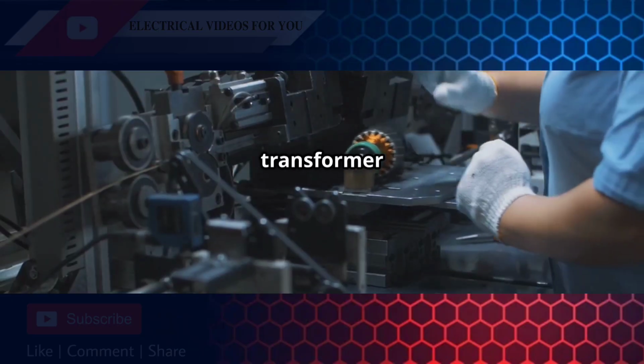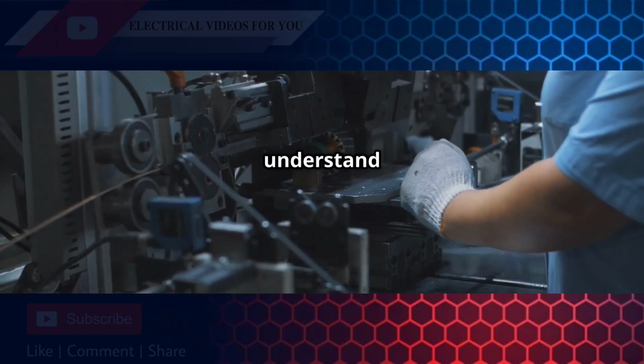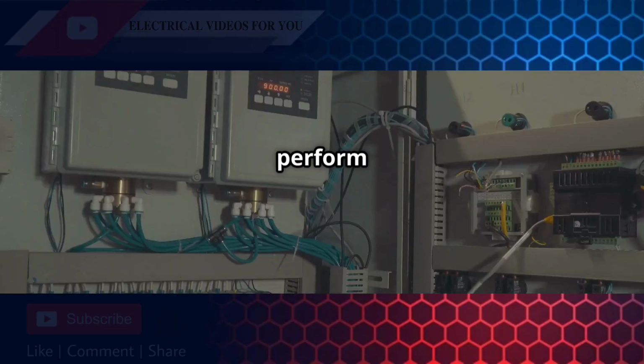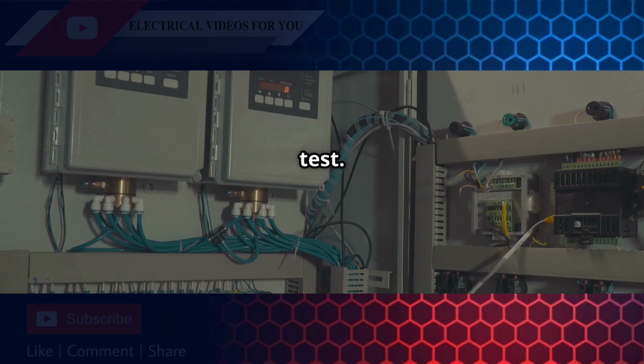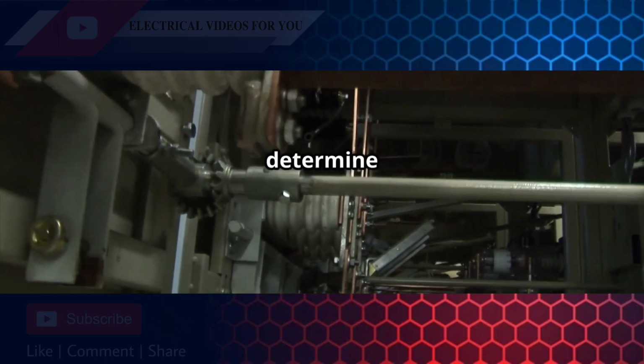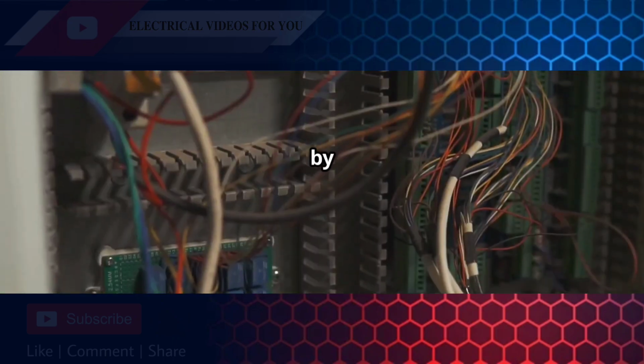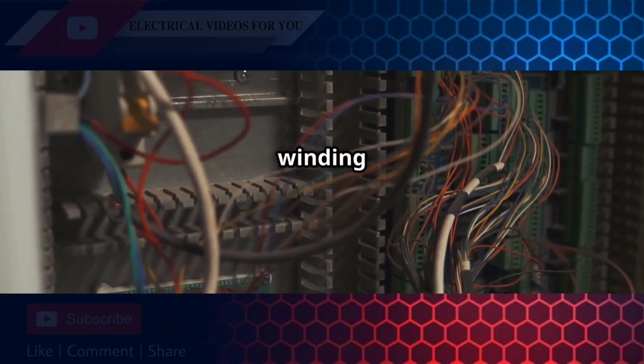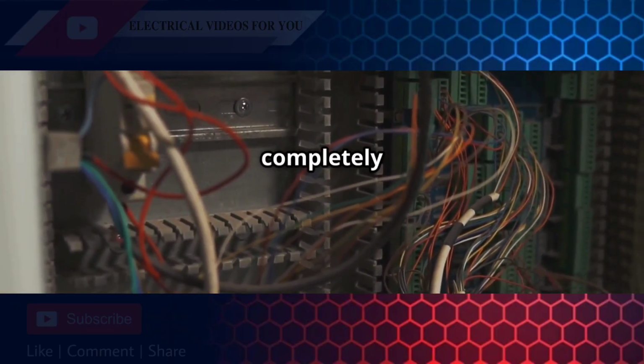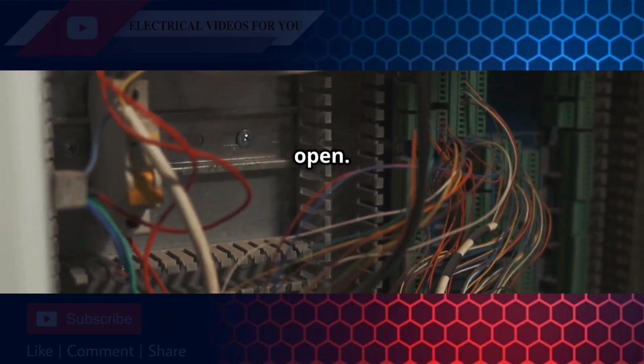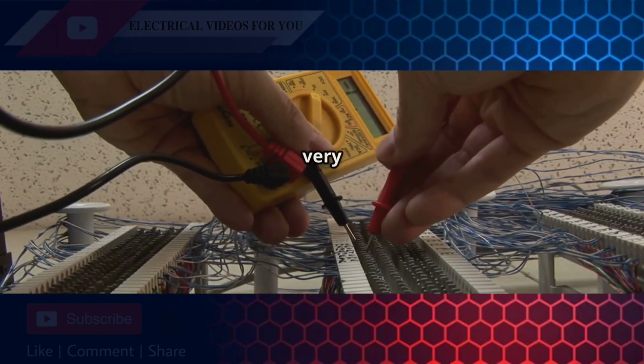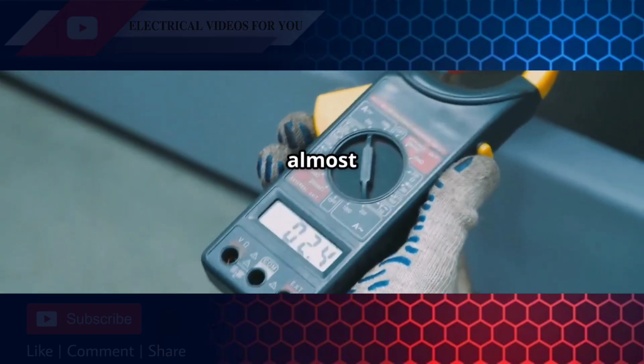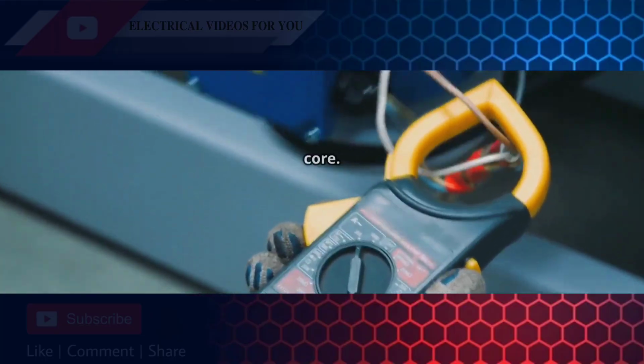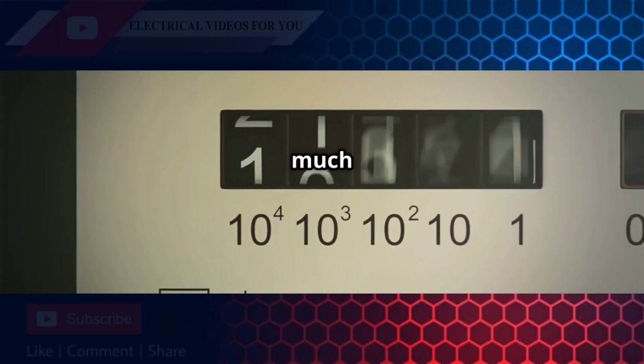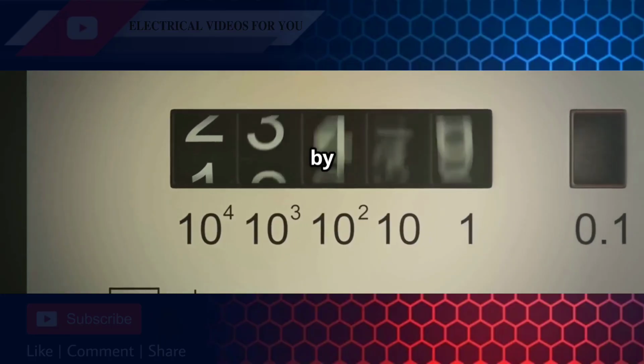To make sure a transformer is working properly and to understand its characteristics, engineers perform two key tests: the open circuit test and the short circuit test. The open circuit test helps determine the iron losses. It's done by applying the rated voltage to one winding while leaving the other winding completely disconnected or open. Since there's no load, the current is very small, and the power measured is almost entirely due to the losses in the core. It's like checking how much energy the transformer uses just by being turned on.